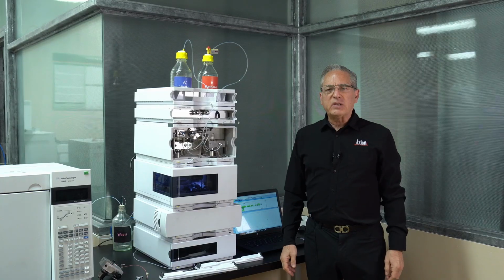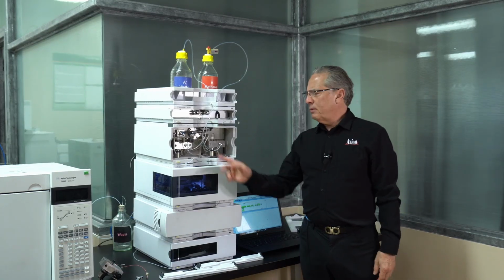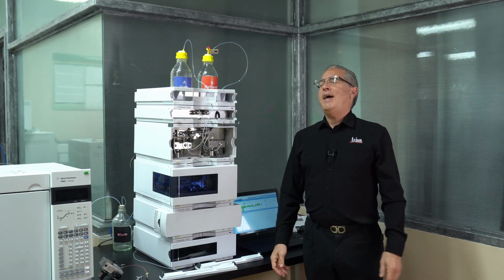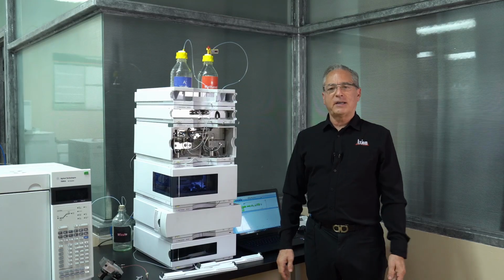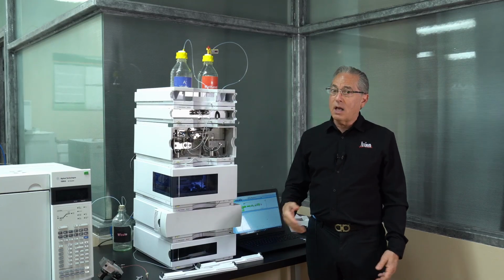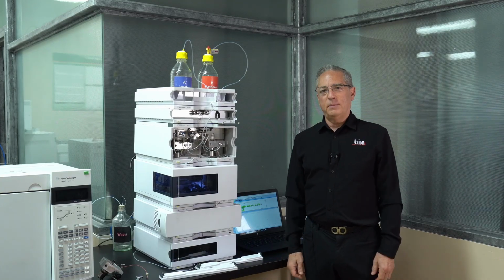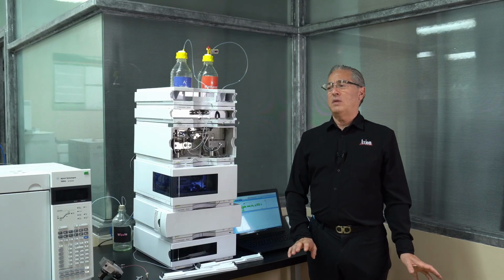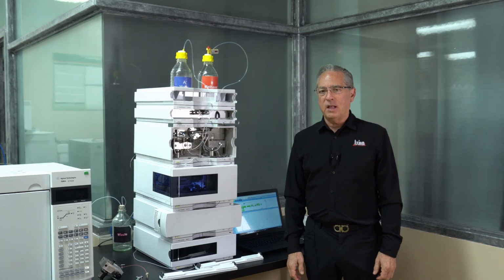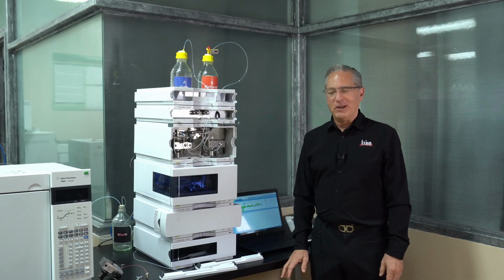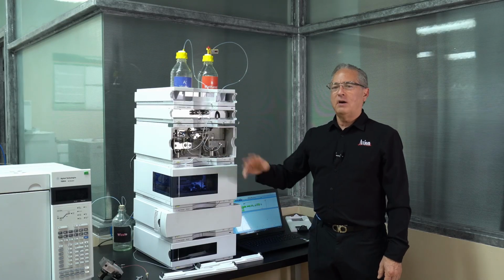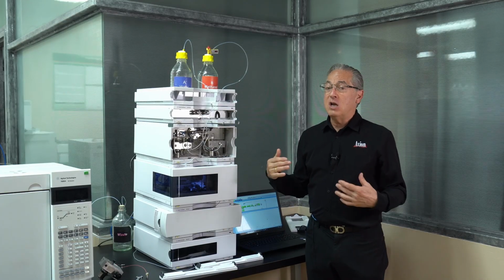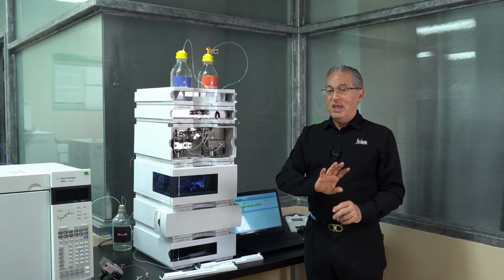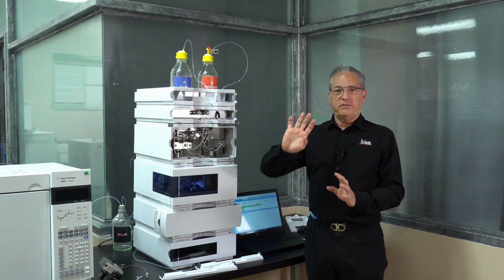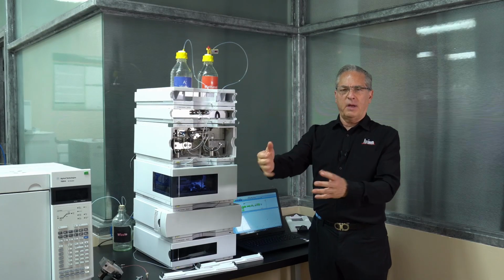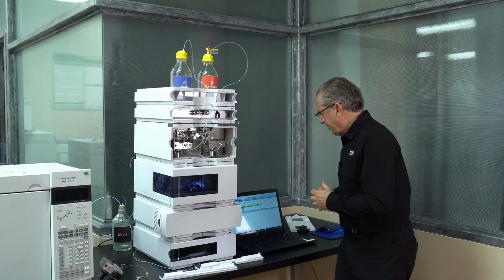By the way, some people will say, never do that. Don't ever pressure shock a column. Don't ever just open the pressure up. That's nonsense. You cannot damage a column. Silica-based columns, all the columns we use today, I used to pack columns. If you ever saw the extreme conditions we use for packing columns, you'd never worry about breaking a column in your lab. So opening it up, high pressure, low pressure, pressure shocks are a non-issue today with silica-based columns. If you're doing gel filtration, gel permeation, fragile columns, yeah, you've got to be careful there. But the rest of us, we don't worry about that.